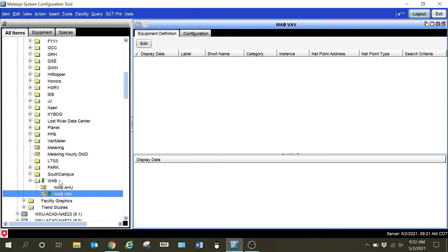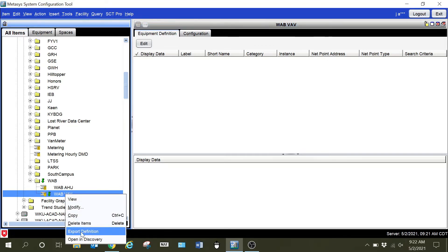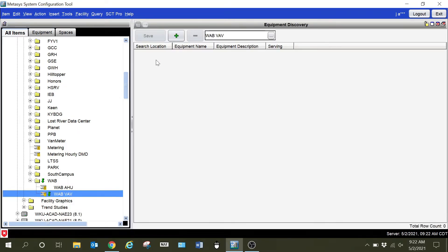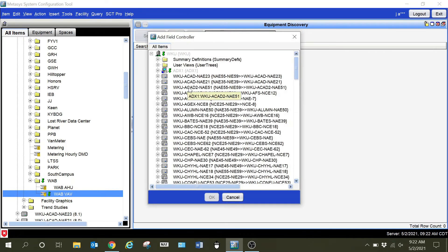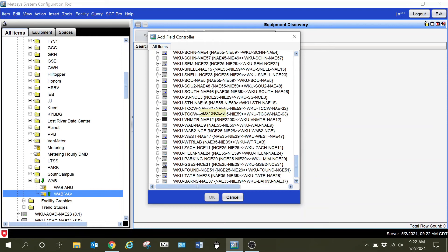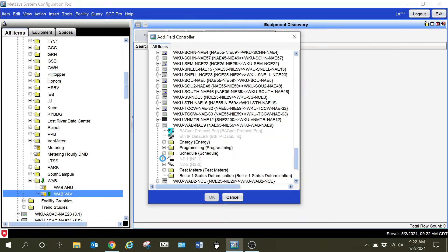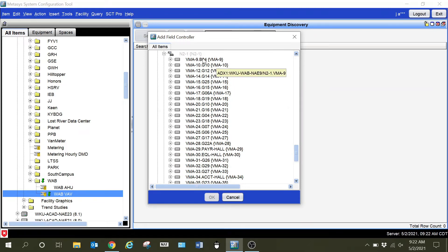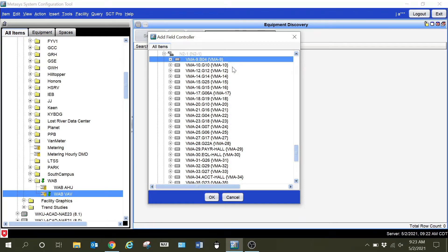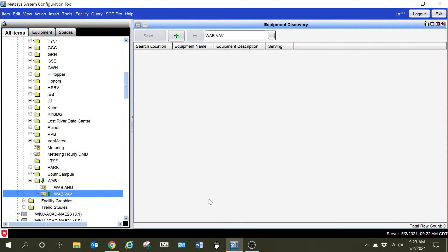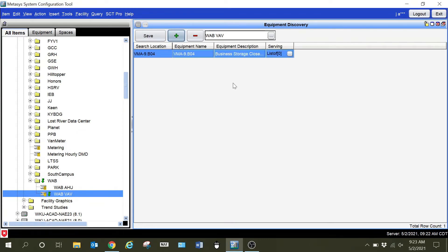I'm going to right-click it and open in Discovery. That's going to give me this screen here — this is where I'm going to add the device I want to the system. I'm going to hit the plus sign and drill down through the navigation tree until I find the particular device I want. I'm basically going to grab one of the VAVs. It has been my experience that you want to start by grabbing just one device before you grab a group of them. When I tried grabbing a group without having one in here first, it did not populate the points the way that I wanted.